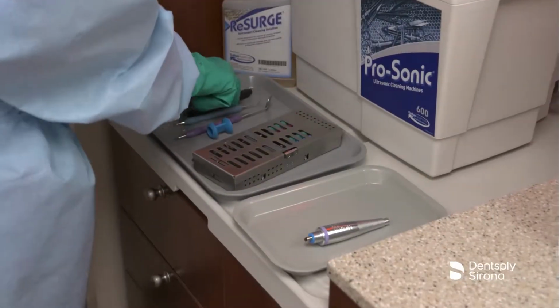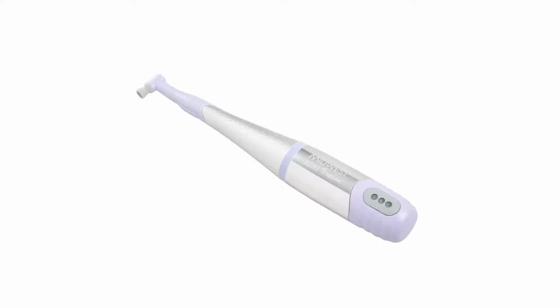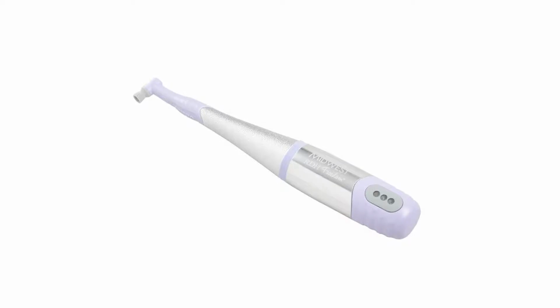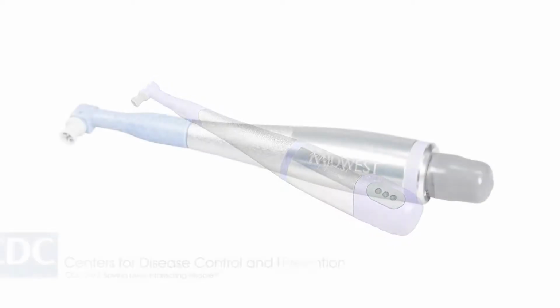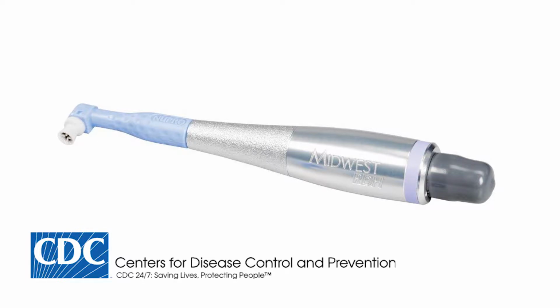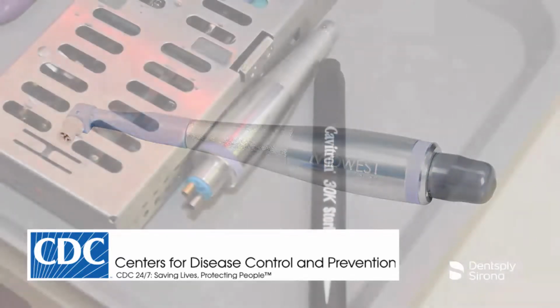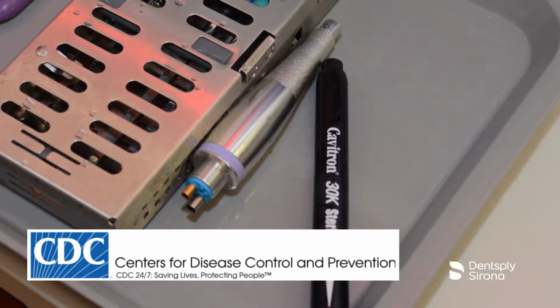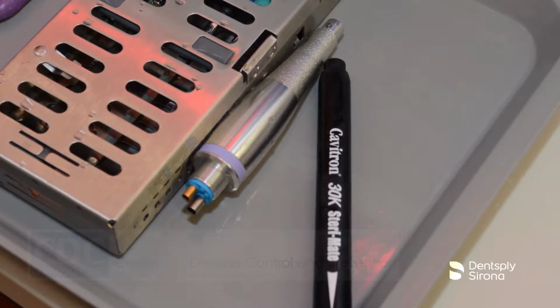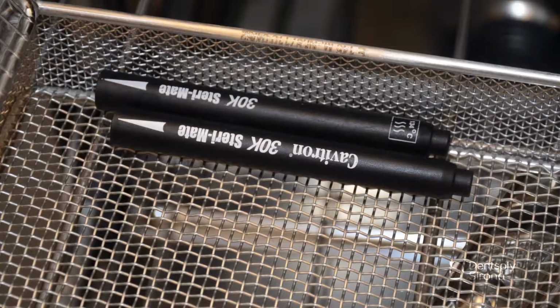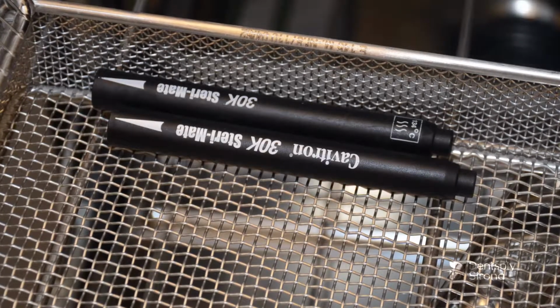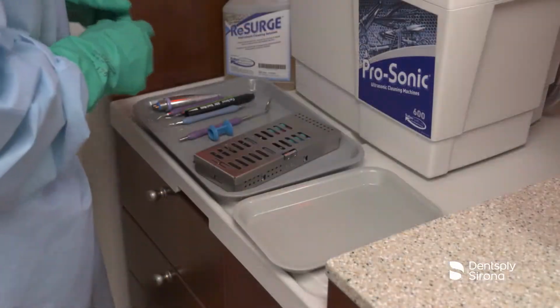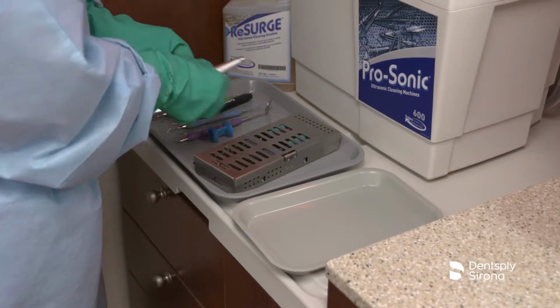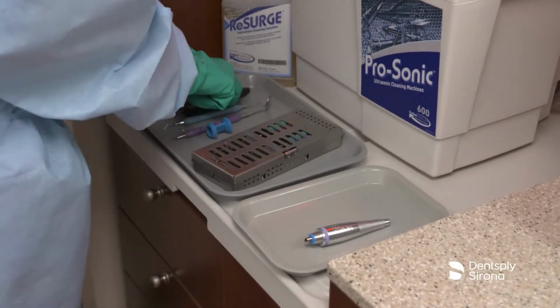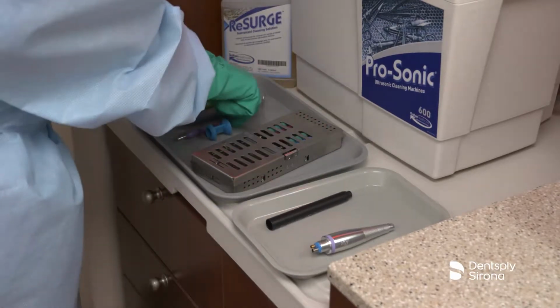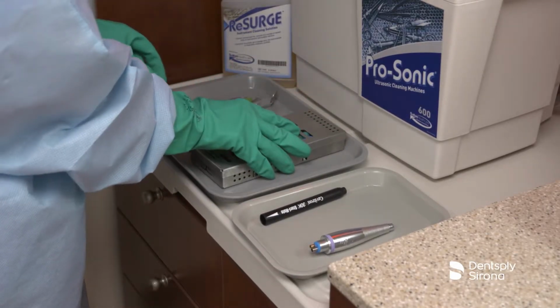Various types of handpieces are utilized daily in dentistry. All require different care to maintain the life of the handpiece. The CDC's recommended guidelines for reprocessing of handpieces requires heat sterilization methods to sterilize handpieces and all devices that attach to air or water lines. It is important to follow the manufacturer's recommendations for cleaning, lubrication, and sterilization of handpieces being used. Once handpieces have been separated from instruments for reprocessing and the manufacturer's guidelines have been reviewed, reprocessing should begin to prevent any residue or contamination from drying on the device.